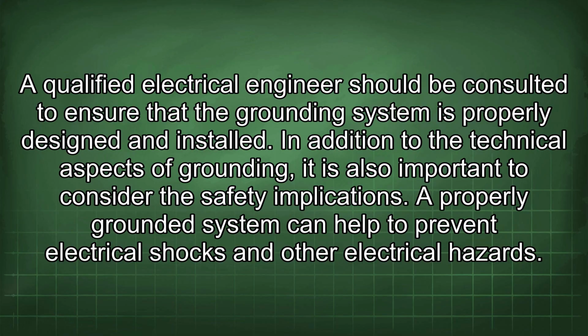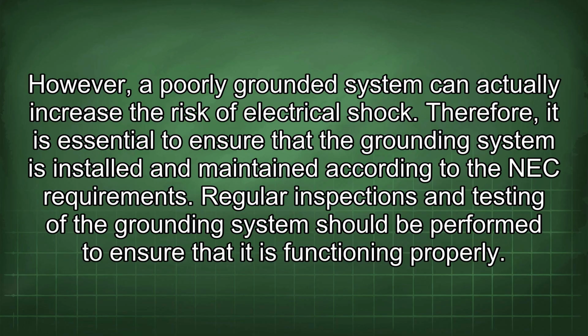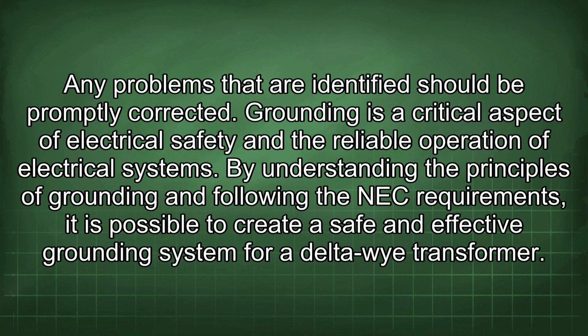In addition to the technical aspects of grounding, it is also important to consider the safety implications. A properly grounded system can help to prevent electrical shocks and other electrical hazards. However, a poorly grounded system can actually increase the risk of electrical shock. Therefore, it is essential to ensure that the grounding system is installed and maintained according to the NEC requirements. Regular inspections and testing of the grounding system should be performed to ensure that it is functioning properly. Any problems that are identified should be promptly corrected.